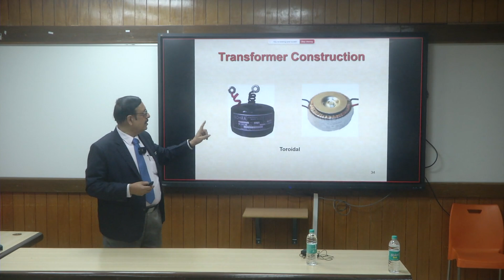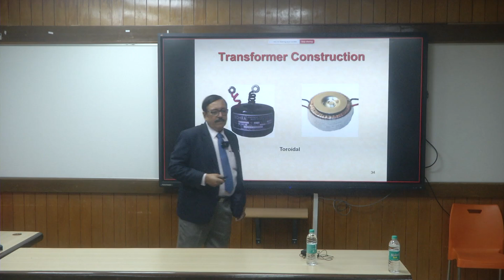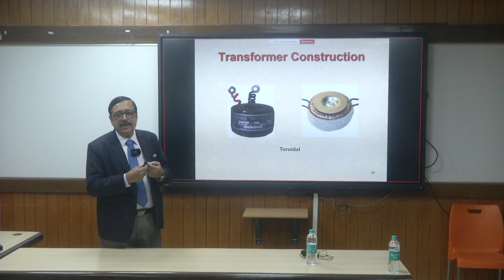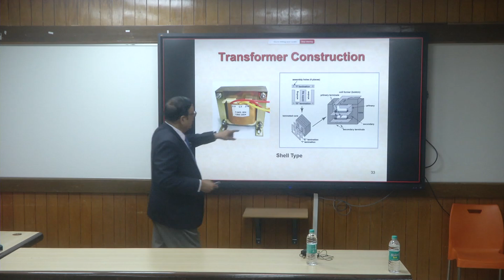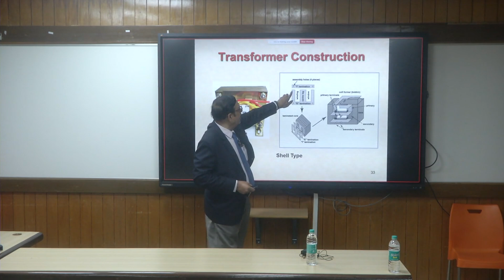All toroidal core constructions are prone to high inrush currents. The inherent construction does not have any air gap anywhere along the path length. So when you make your switch on, it can go through a huge inrush current and there's hardly anything limiting it. Why doesn't it happen in this? Because of the small gap here, maybe a fraction of a millimeter air gap at the joint, that limits the inrush current because the reluctance of air is quite large there. You have a joint, so the joint is also helpful in limiting inrush current.